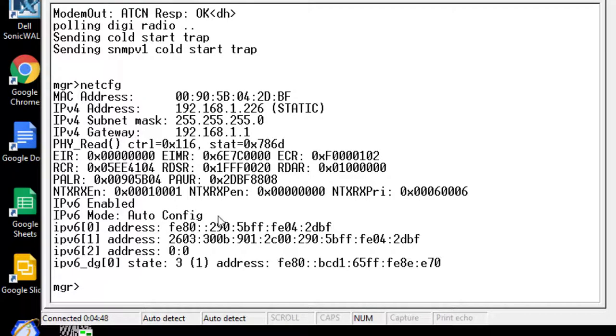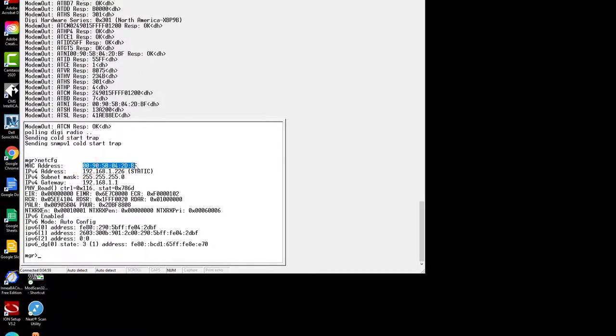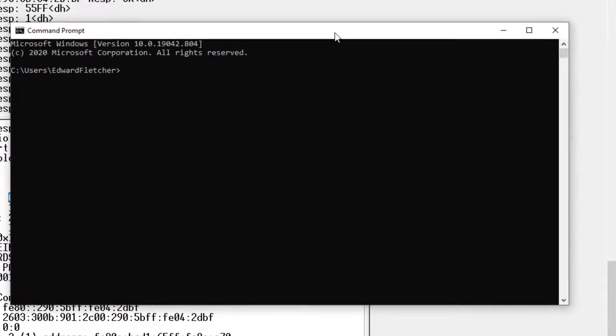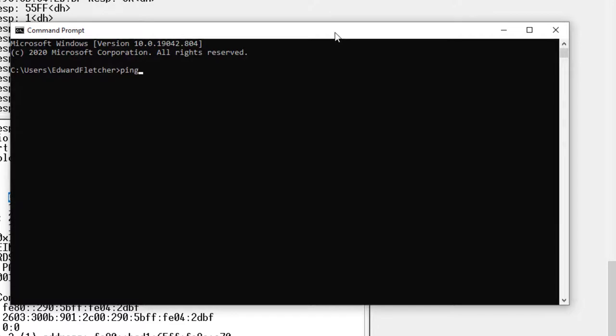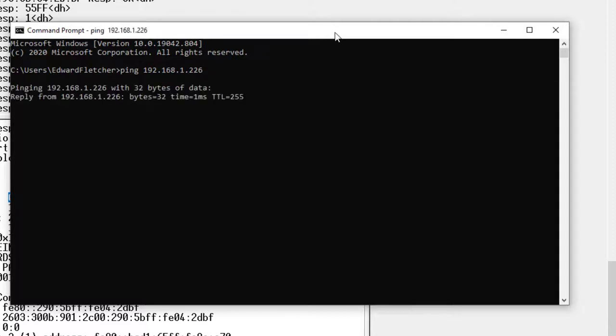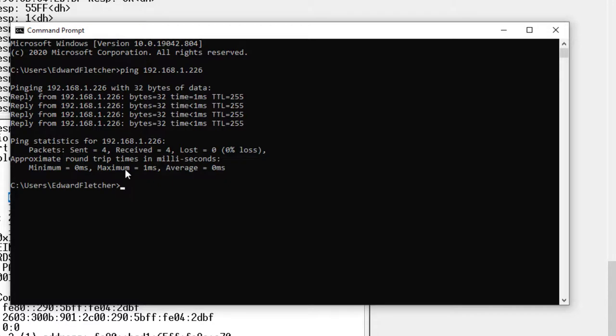Now that we have this configured, depending on your company's policy, you might have to work with your network group doing a port turn up on a switch. You might have to furnish them this MAC address, potentially, along with the IP, letting them know what port you're plugged into for doing a proper port turn up. On this one, I have very light security built across. So I'm going to come to my command prompt, open it, and make sure that it's talking on the network. So you do ping 192.168.1.226. I'm testing this from my PC that resides on the network, so it's not a direct connect. This will test the connectivity that we have communications. That is the perfect sign you like to see.